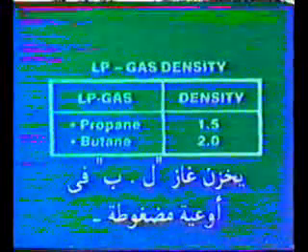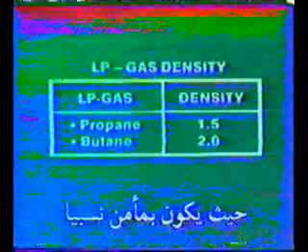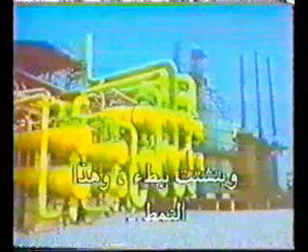Let's look at the vapor characteristics of two other common industrial fuels, LP gas and natural gas. LP gas is primarily composed of propane and butane, which are both heavier than air. Normally, LP gas is stored in sealed, pressurized containers where it's relatively safe. But if a gas leak occurs, the vapors will hang near the ground and are slow to disperse. This type of release presents a serious fire or explosion hazard, especially if there are any sources of ignition in the vicinity of the spill.